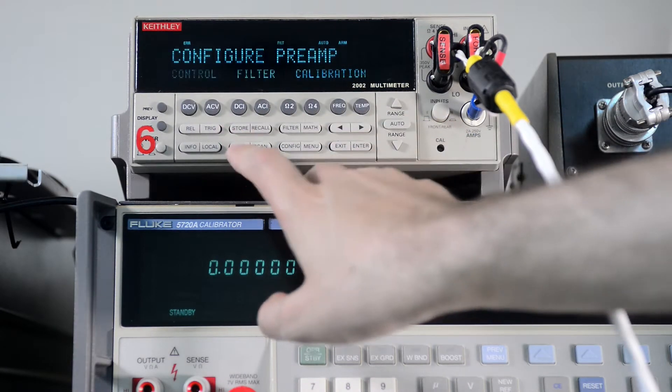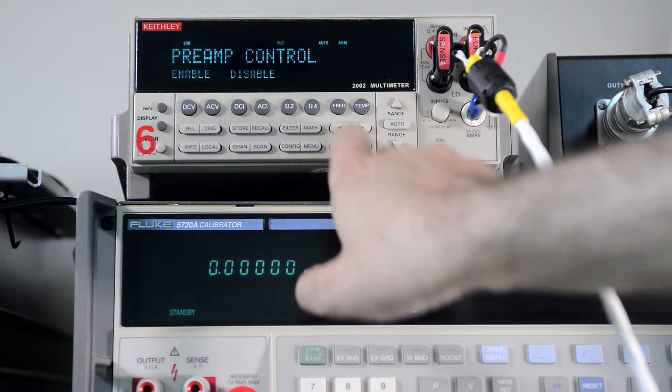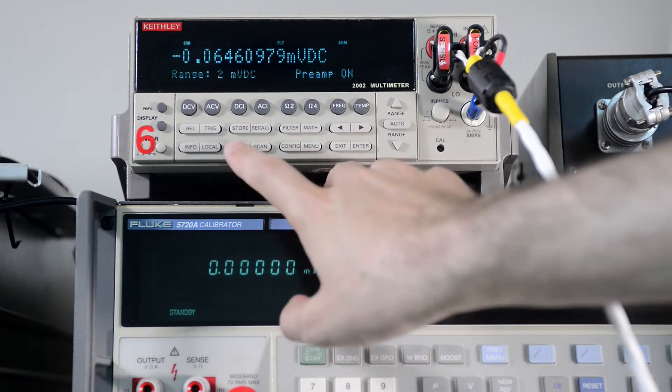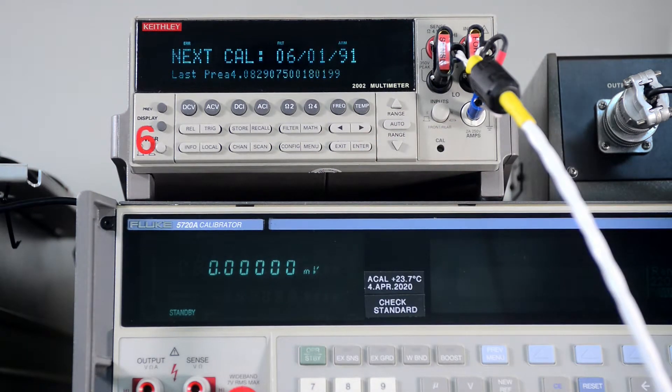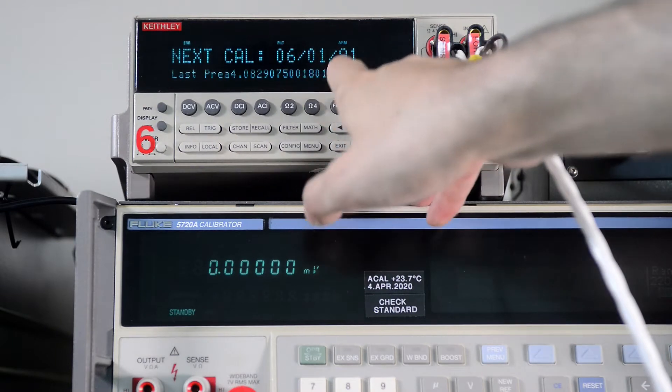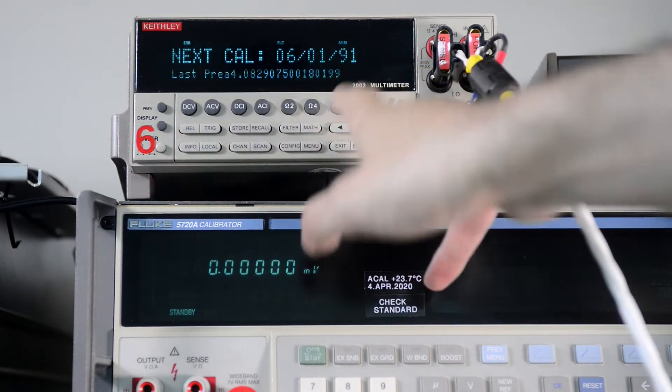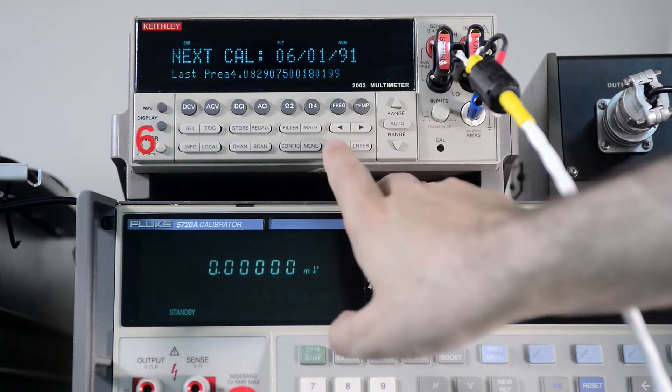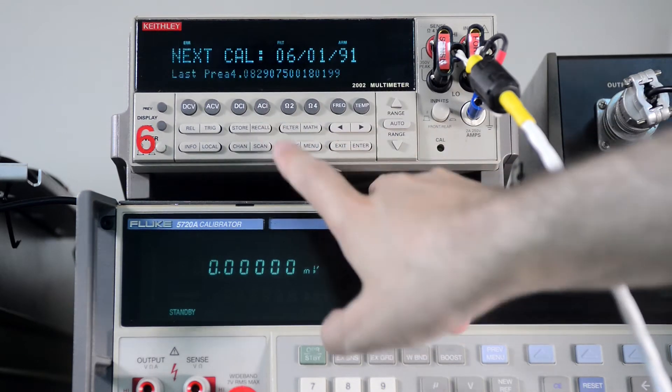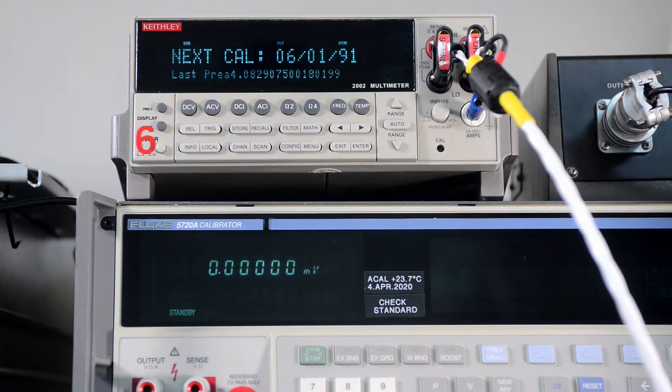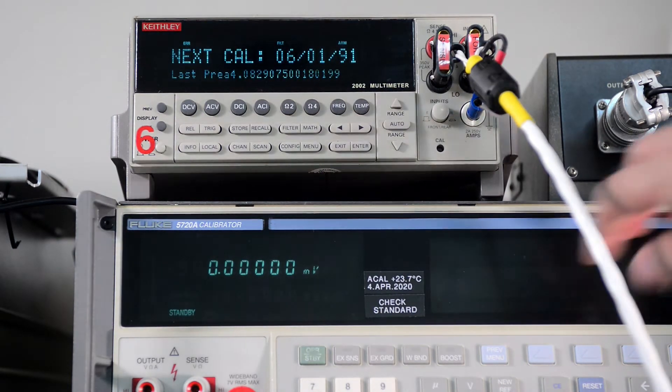I can enable it using the onboard menu. So now the pre-amplifier is enabled and we can see the calibration date. Next calibration is just default value 06/01/91 and here you see some random values because it doesn't read last calibration from the correct EEPROM field, I think.